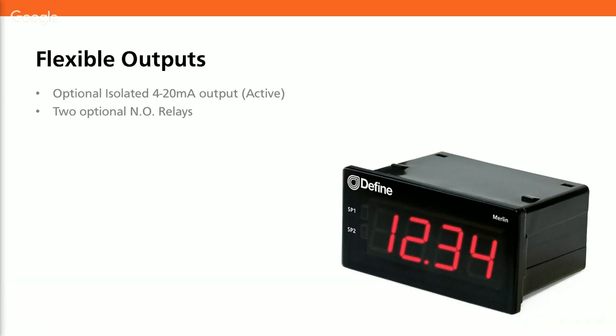The Merlin also has flexible outputs as an optional extra. The output is a 4 to 20 milliamp loop output that is active. This means that the power for the loop is coming from the Merlin itself, so you don't need any external power supplies to power your sensor loop.